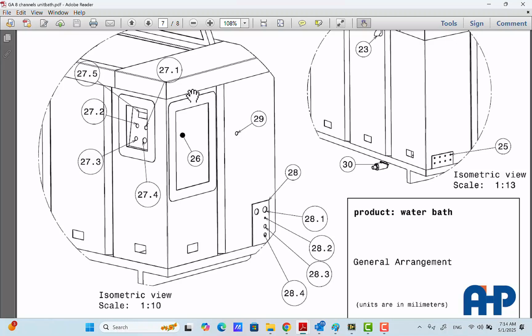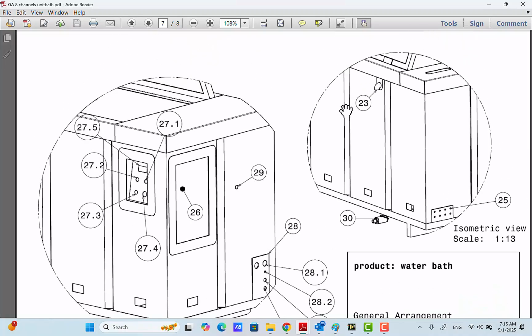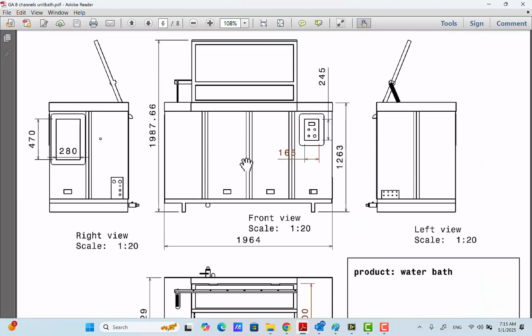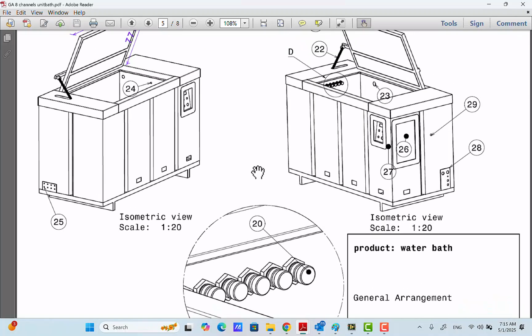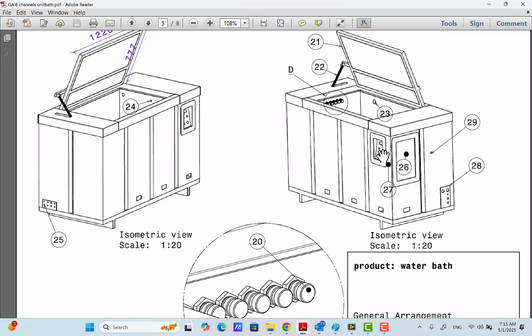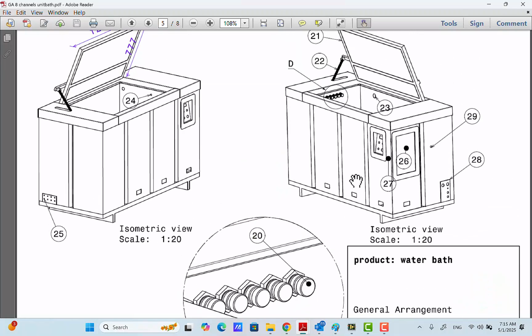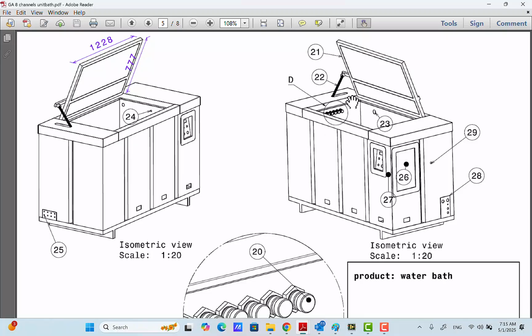because in shipments, in some cases, the stuff is just put inside the tank. You need to remove them before the start of the testing and installation. That's why this key is not electrical, because before filling the tank from the top with water, you need not to connect the electricity, and you need not to start the machine running. Of course, it will cause failure of the heaters. That's why for the first run, for the first startup, you need to fill the tank from the top.